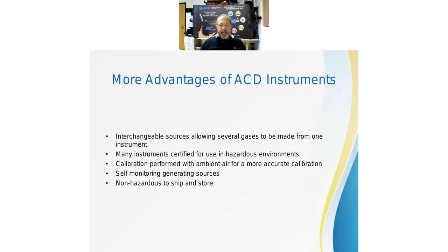Say it's nitrogen dioxide, and we feel that's the most accurate way to calibrate a sensor, rather than a permeation tube or a cylinder. Typically a corrosive gas like NO2 is going to be stored in nitrogen, so it's no humidity, pure nitrogen, and the sensor will react a little bit differently to that than it will to the ambient air in the room with its relative humidity blended with the calibration gas that you're looking for. In our case, we're talking about NO2 this time, but that's the most accurate way we believe to calibrate. That would simulate what a leak in that room would look like, right?